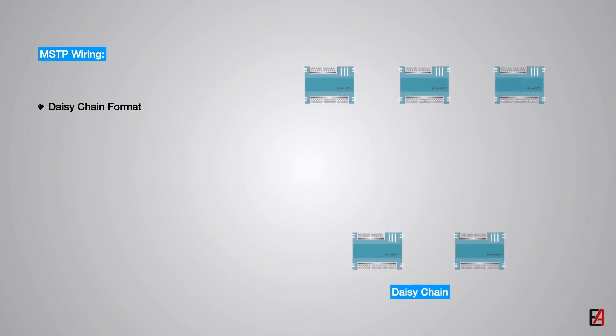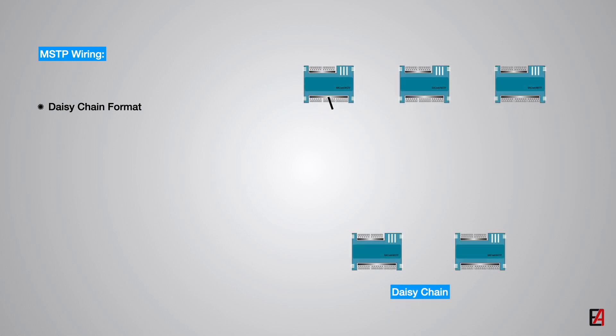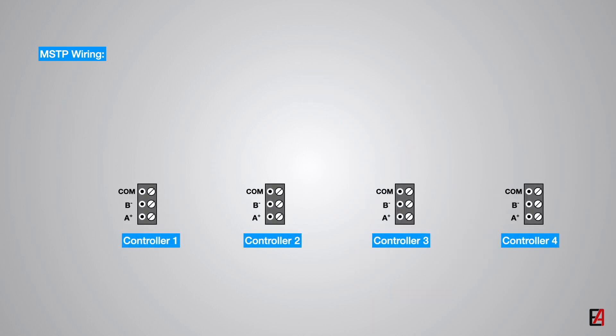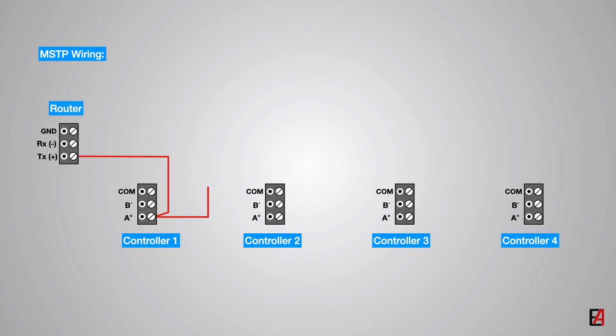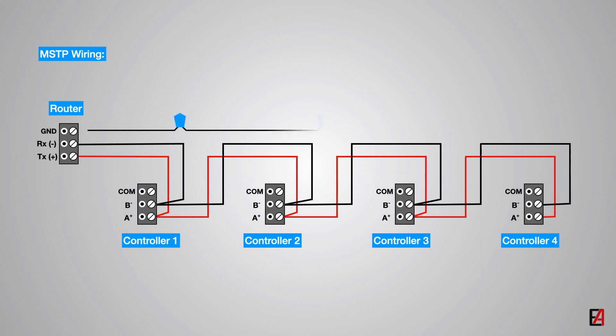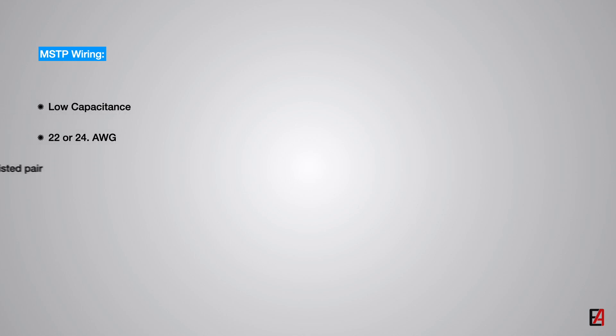The MSTP network must be installed in a proper daisy chain format. daisy chain configuration means that there is only one main cable and every network device is connected in parallel directly along its path. The correct MSTP wiring with daisy chain format is shown here. It is important to keep the same color for all A-plus terminal wiring and different color for B-minus terminal. The shield wires must be grounded only on one side. The recommended cable specification shall be low-capacitance 22 or 24 AWG shielded twisted-pair cables such as Belden 9841.